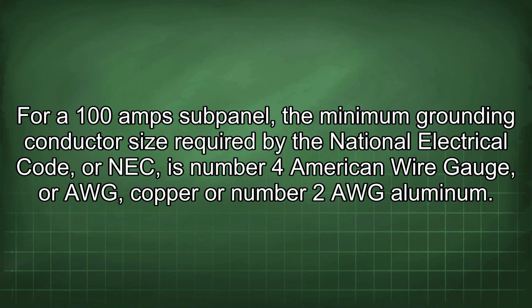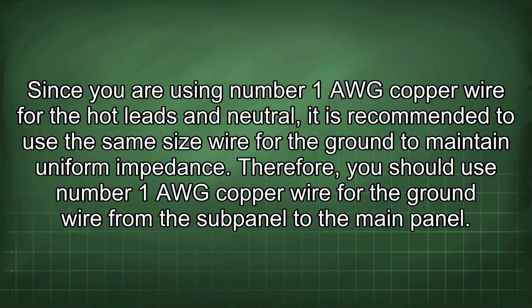For a 100 amp subpanel, the minimum grounding conductor size required by the National Electrical Code, or NEC, is number 4 American wire gauge, or AWG, copper, or number 2 AWG aluminum. Since you are using number 1 AWG copper wire for the hot leads and neutral, it is recommended to use the same size wire for the ground to maintain uniform impedance. Therefore, you should use number 1 AWG copper wire for the ground wire from the subpanel to the main panel.